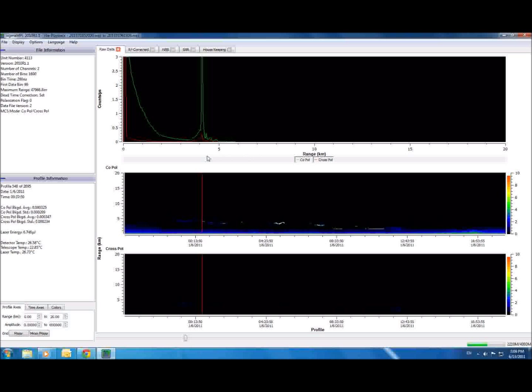An individual dataset, or profile, appears as a line graph here in the center top portion of the window. This graph displays the photon counts received by the detector in relation to the distance each back-scattered photon traveled before being reflected.